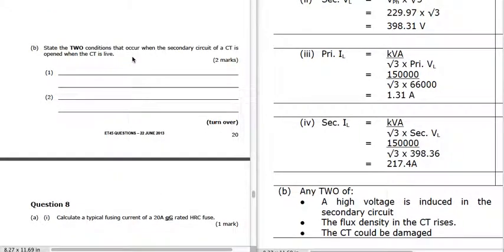If the secondary circuit of a CT is opened when the CT is live, you should never have the secondary of a current transformer open-circuited. If you do: a high voltage is induced in the secondary circuit, the flux density in the CT rises, and the CT could be damaged by this high induced voltage.